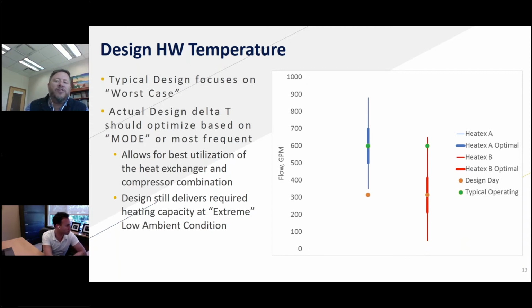But what you end up seeing is then where we actually operate the unit, the lion's share of the time, we're getting close, or in a lot of cases actually exceeding the capability of what that heat exchanger can. Because again, we've got a fixed heat exchanger that's going to see a capacity, an approach, a pressure drop through it. It's all based on how much capacity we're actually doing with our refrigeration effect. And so if we design our systems to that extreme design day, if we're looking at a 100-year extreme, I mean, by definition, that's almost never happening.